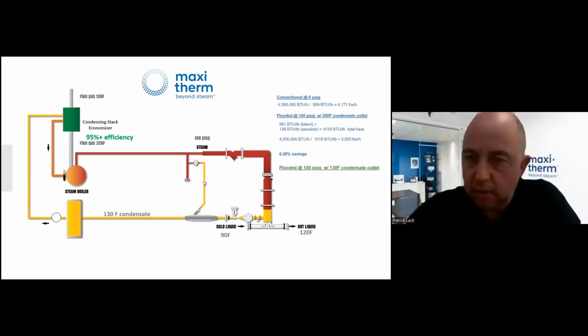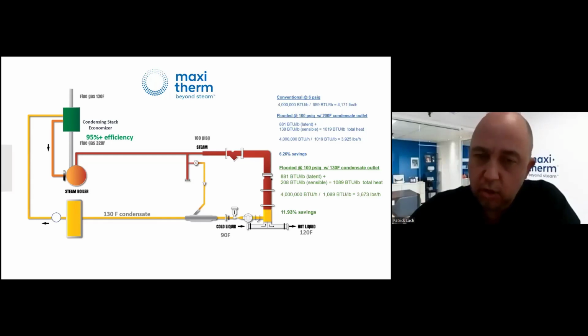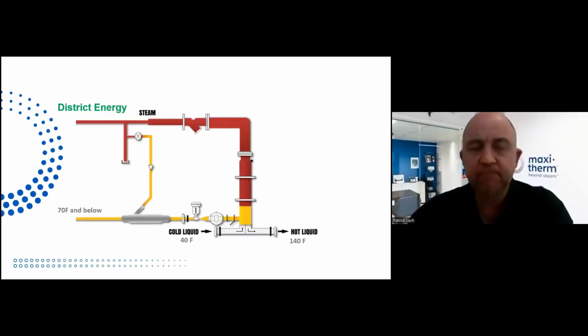What would be the number if condensate is leaving at 130 Fahrenheit? 12%. Twice the savings. So you need 12% less steam at the point of use, and you get 10% plus more efficiency on steam generation. That's the benefit of 100% steam condensate closed loop. Less blowdown, less maintenance, less chemical.